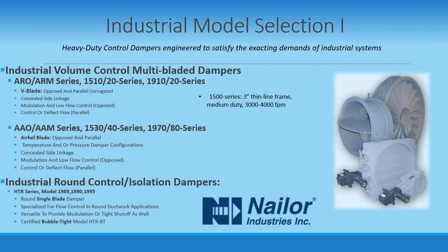As we have seen, the operating parameters will influence each component of the damper. Pressure, flow rate, temperature maxima and minima, and the duct medium are the starting points, followed by performance requirements such as leakage and pressure drop. Once we have this information, we can design the proper damper for the individual application. Our heavy-duty industrial control dampers — multi-bladed, rectangular, and square — begin with the 3-inch deep framed 1500 series and progress into the heavier 1900, AR, and AA series.